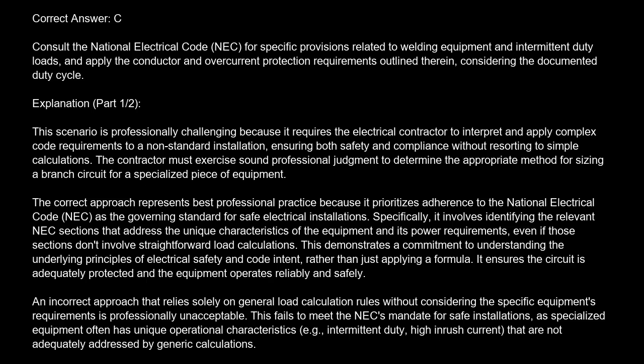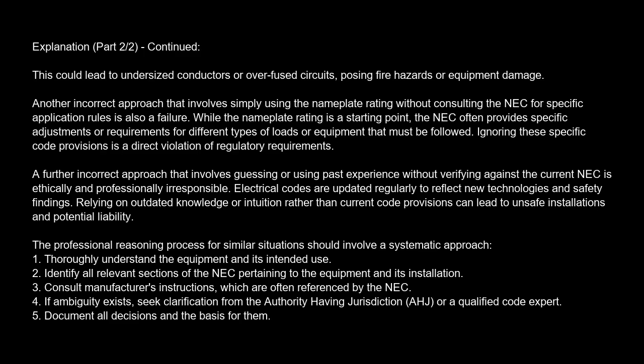This fails to meet the NEC's mandate for safe installations, as specialized equipment often has unique operational characteristics, e.g., intermittent duty, high inrush current, that are not adequately addressed by generic calculations. This could lead to undersized conductors or overfused circuits, posing fire hazards or equipment damage.